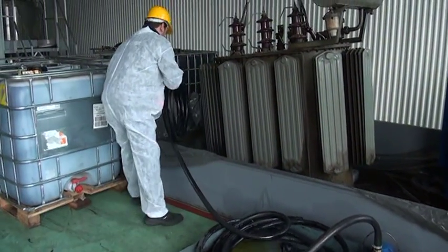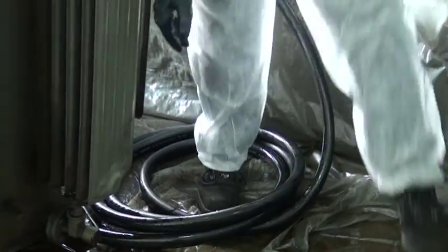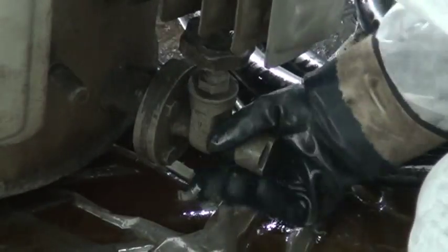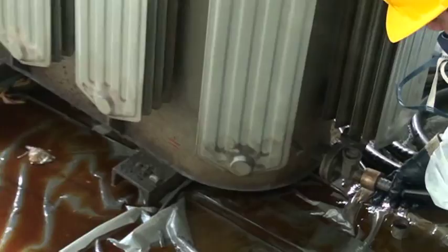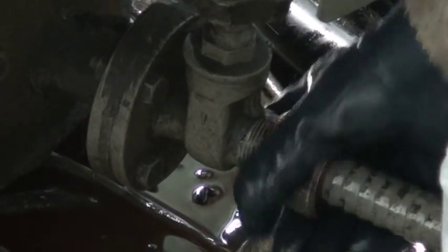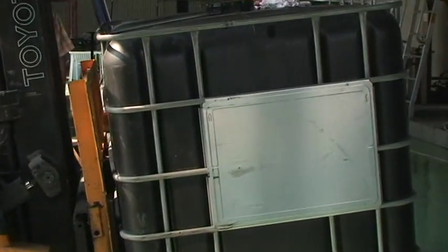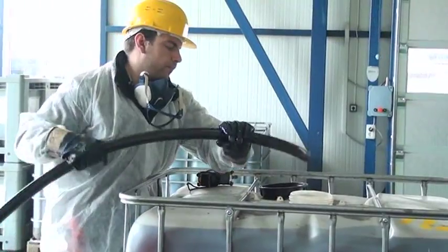Oil draining or emptying. The insulating oil containing PCB is drained from the transformers using the draining pump and stored in plastic containers. The draining activities have to be performed at maximum level in order to minimize the oil amount left in the carcasses.